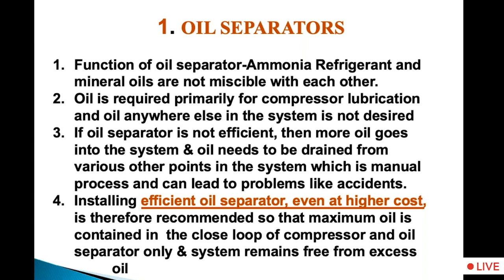So oil is required primarily for lubrication of the compressor and not anywhere else in the system. So it is essential that we keep oil in a closed loop of compressor and oil separator, and therefore the efficiency of the oil separator is very, very important, so that oil is not drained from various points in the system. It can be controlled only within a closed loop of compressor and oil separator, that's all. So installing an efficient oil separator even at higher cost is strongly recommended, so that maximum oil is contained in the closed compressor loop and the system remains free from oil.